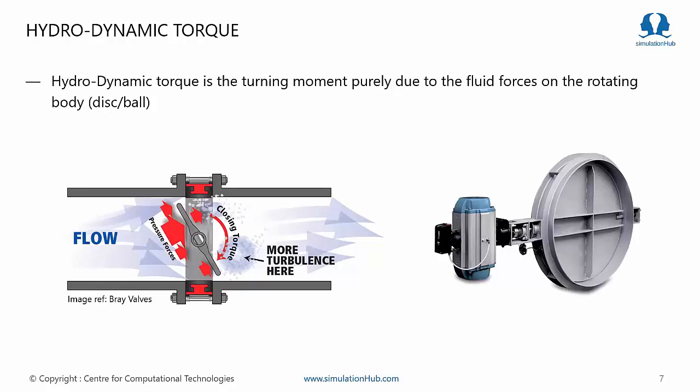Hydrodynamic torque is the turning moment purely due to fluid forces acting on the rotating body. Consider a concentric butterfly valve where the disc is partially open and flow is happening from left to right. When the fluid crosses the disc, the velocities at the leading edge and trailing edge are different, creating an unbalanced pressure force on both sides of the disc. This causes a closing torque, and that is where the actuator comes into picture.